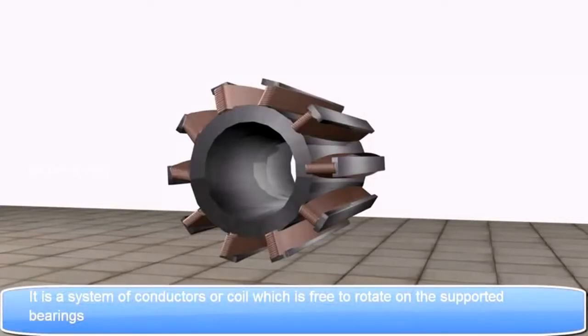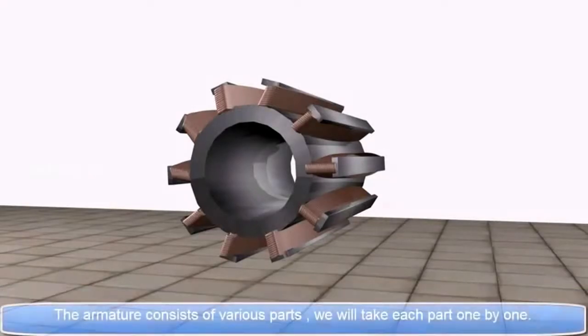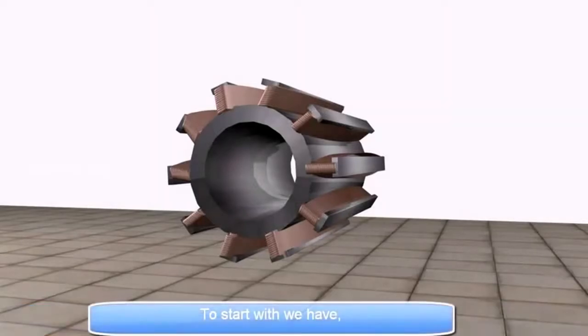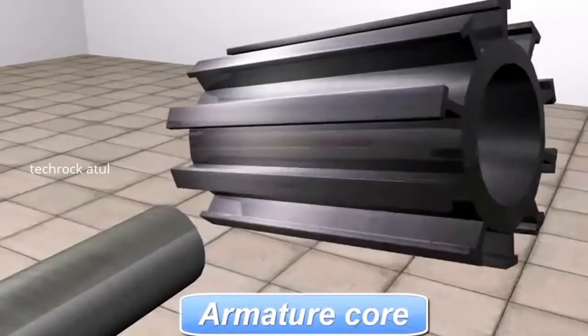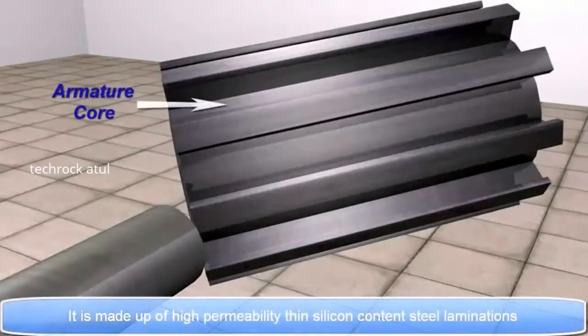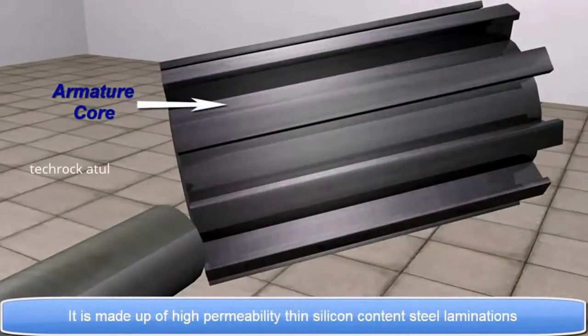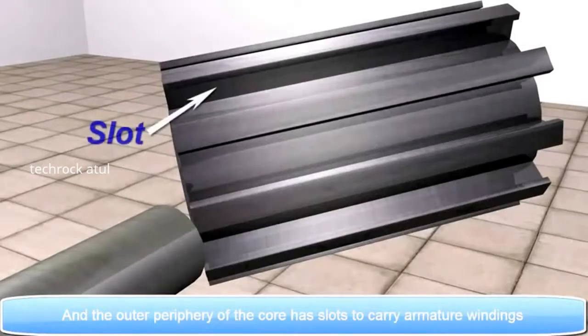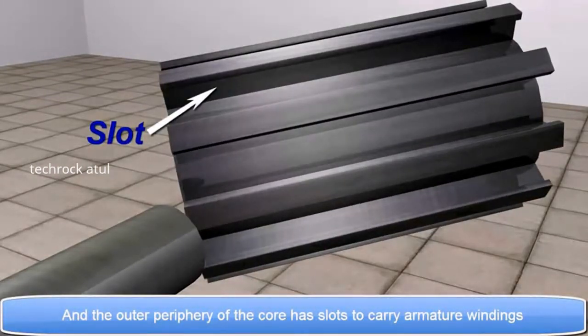Armature. It is a system of conductors or coil which is free to rotate on the supported bearings. The armature consists of various parts. We will take each part one by one. To start with we have armature core. It is made up of high permeability thin silicon content steel laminations. And the outer periphery of the core has slots to carry armature windings.